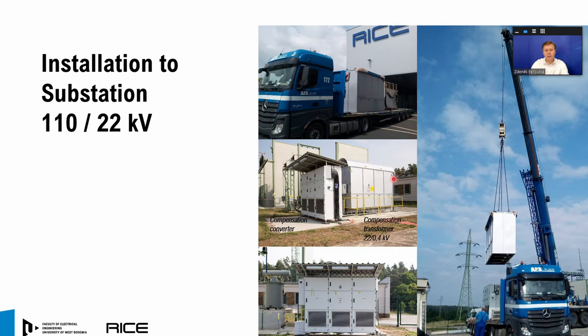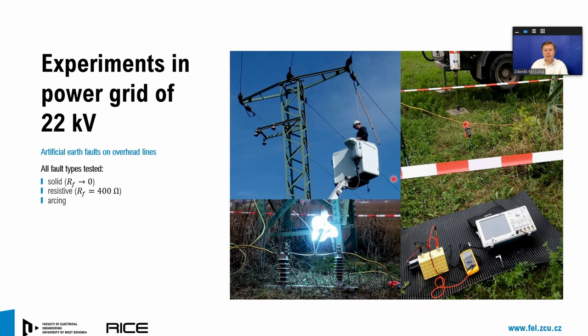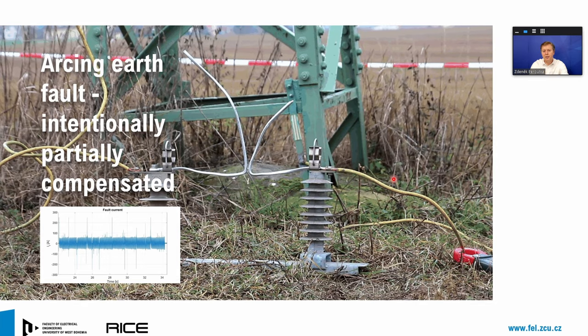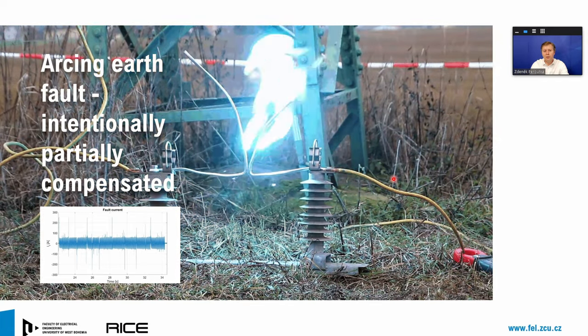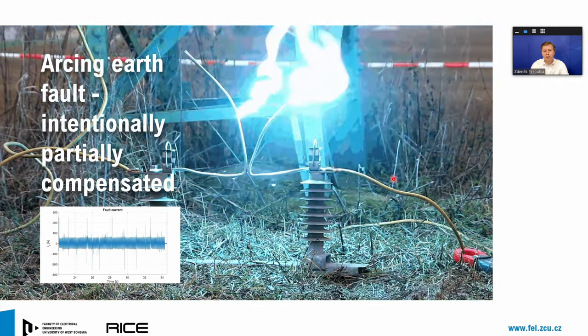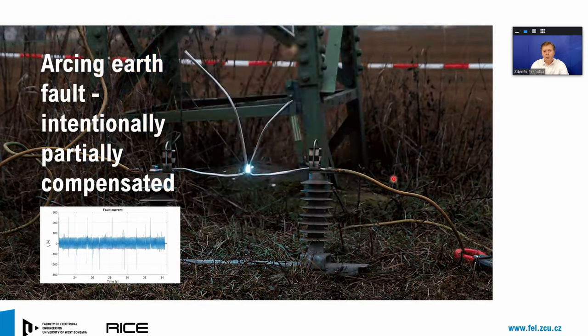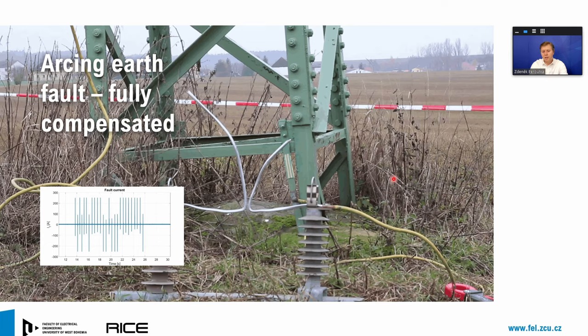After the laboratory test, we installed our prototype in a 110 to 22 kV substation and started the tests in the field. We started with artificial earth faults on overhead lines. We did tests of all fault types: solid, resistive, as well as arcing. Here you can see an illustration video of what happened when you face an arcing earth fault, which was intentionally only partially compensated. And in the second video, you can see the behavior of the system when our device fully compensates the ground fault.